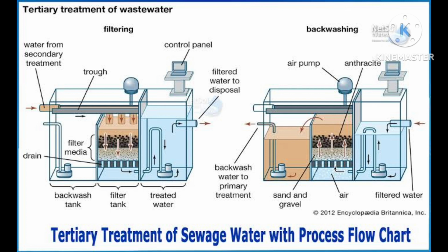Now water became high clarity. Treated water has high clarity, free from odor, low BOD. Low BOD means biological oxygen demand that is less than 1 ppm. It is very good, just like normal water. BOD now became less than 1 ppm.